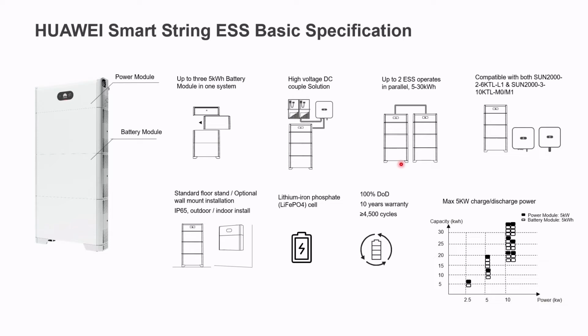But remember one thing, it's like a DC coupled solution. The output power of the system is always limited by the maximum output power of the inverter. So even if you have a 30 kilowatt hour system but a 10 kilowatt inverter, it will always be limited to the maximum output power of the inverter, which is 10 kilowatts. So this is, let's say, a disadvantage of this solution.